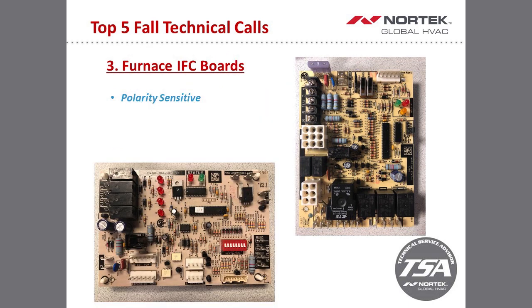With our boards, in regards to flame sense, they are polarity sensitive, meaning that when you do hook this up on a new installation, you need to have your L1, your 120 volts going to L1 on the board, and neutral needs to go to neutral. I know that seems very simple when I explain it, but we do get lots of calls on polarity questions. If you come up on a troubleshooting call where the furnace has been installed for a while, where it's not a new install and you do get a polarity fault, that is generally a new board scenario.